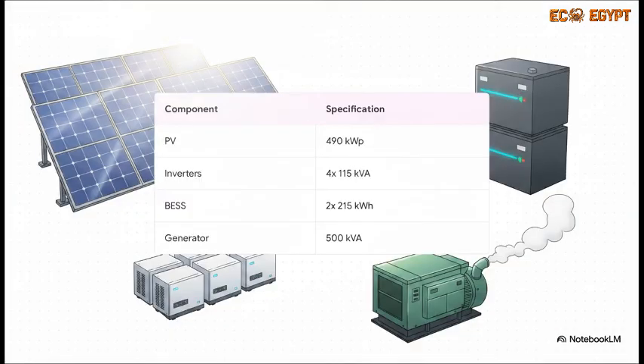Here are the final engineering deliverables for the project. For the PV plant, we have 792 modules, giving us 490 kilowatts peak. We balance that DC capacity with 4x115 kVA inverters for 460 kilowatts of AC capacity. We paired this with two massive 215 kilowatt-hour BESS units. And finally, based on our strict derating steps, the diesel generator was precisely calculated at 500 kVA, enough to handle the inrush, but loaded enough to avoid wet stacking.